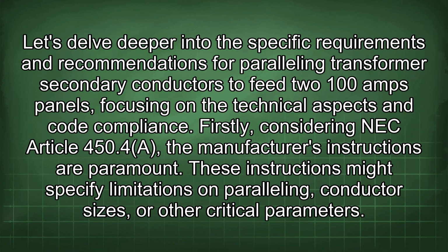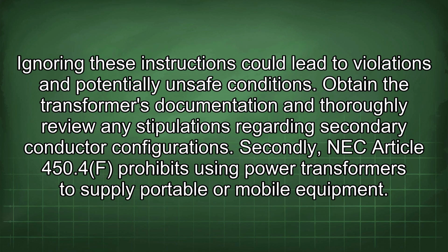Let's delve deeper into the specific requirements and recommendations for paralleling transformer secondary conductors to feed two 100 amp panels, focusing on the technical aspects and code compliance. Firstly, considering NEC Article 450.4a, the manufacturer's instructions are paramount. These instructions might specify limitations on paralleling, conductor sizes, or other critical parameters. Ignoring these instructions could lead to violations and potentially unsafe conditions. Obtain the transformer's documentation and thoroughly review any stipulations regarding secondary conductor configurations.